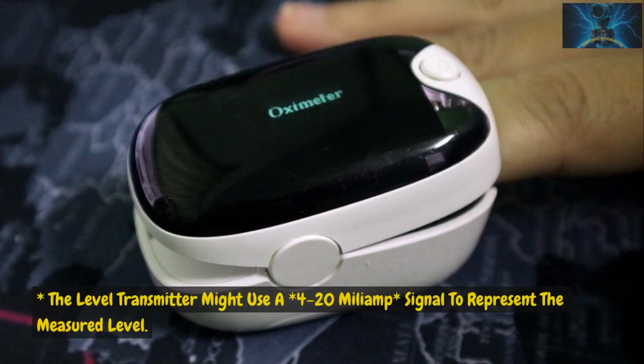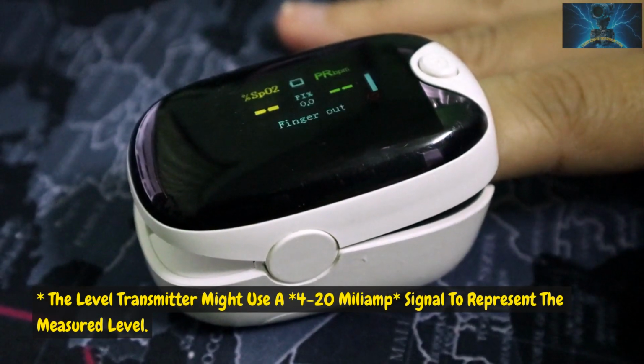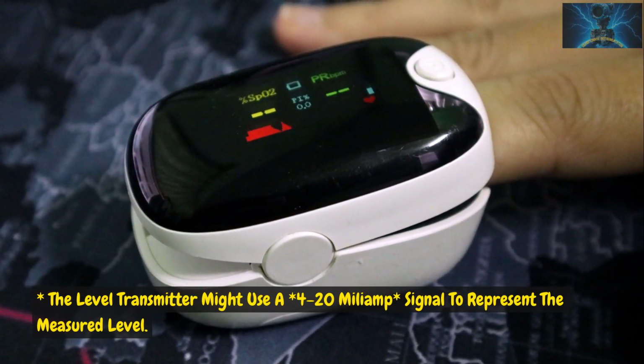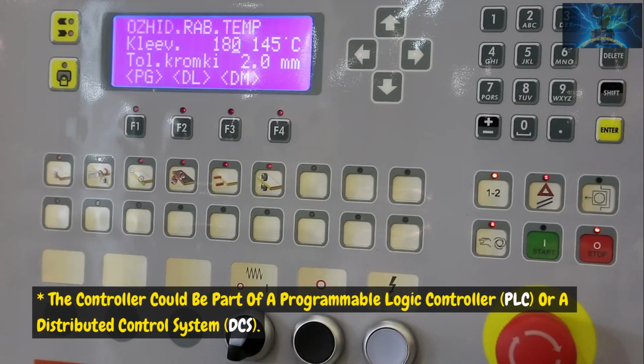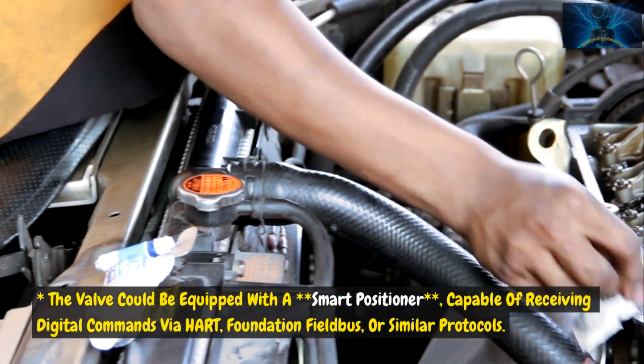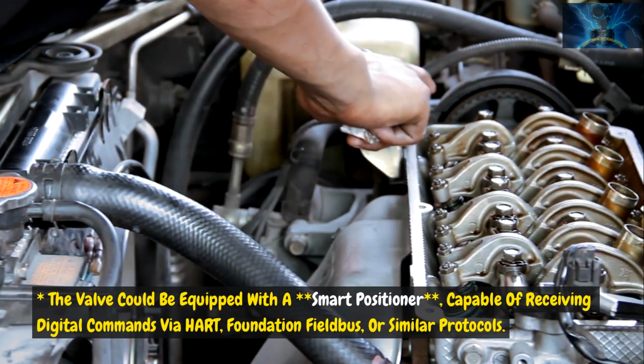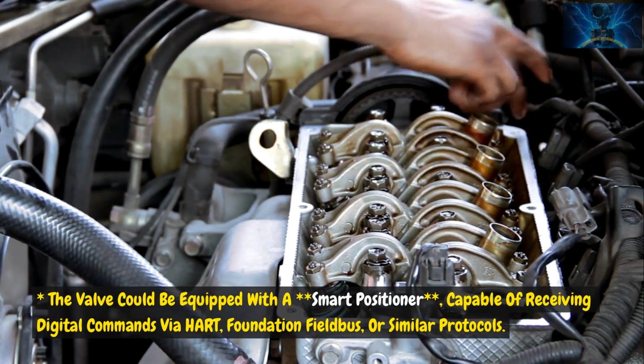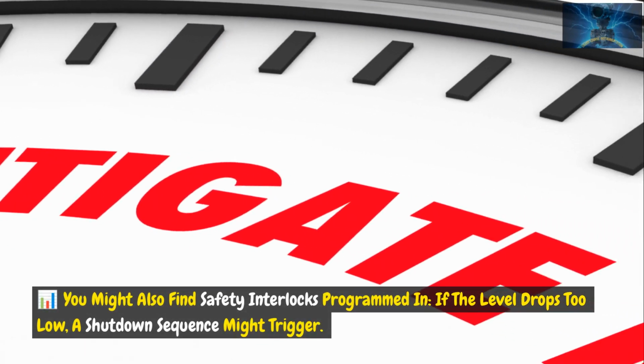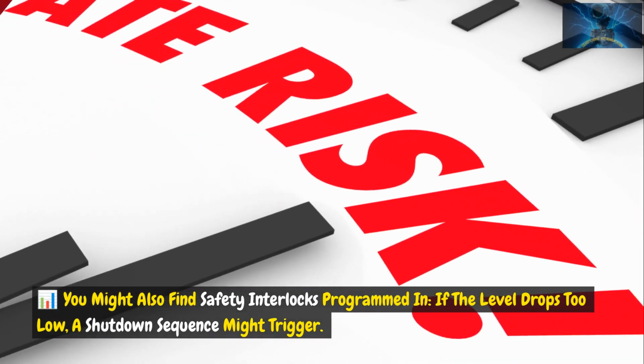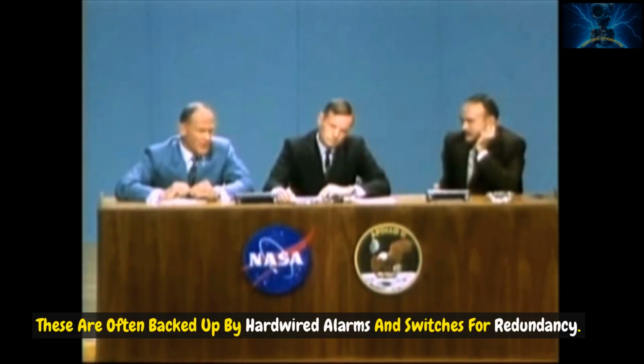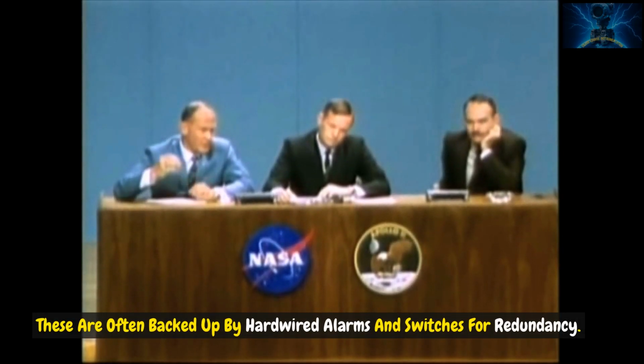In many modern systems, this signal chain is digital. The level transmitter might use a 4-20 milliamp signal to represent the measured level. And the controller could be part of a programmable logic controller, PLC, or a distributed control system, DCS. And the valve could be equipped with a smart positioner, capable of receiving digital commands via HART, Foundation Fieldbus, or similar protocols. You might also find safety interlocks programmed in. If the level drops too low, a shutdown sequence might trigger. These are often backed up by hardwired alarms and switches for redundancy.